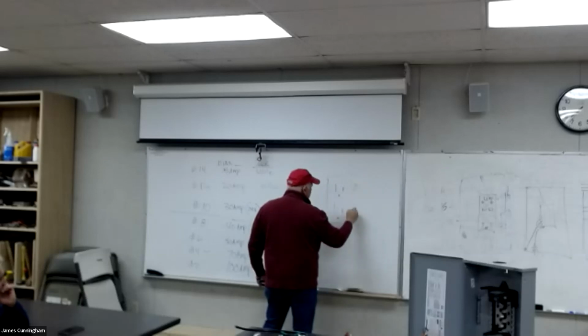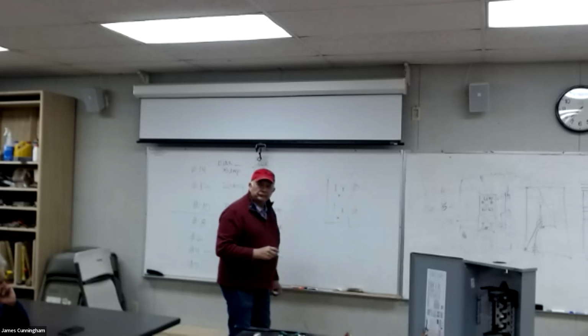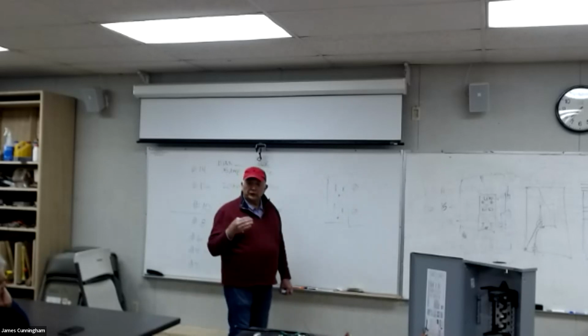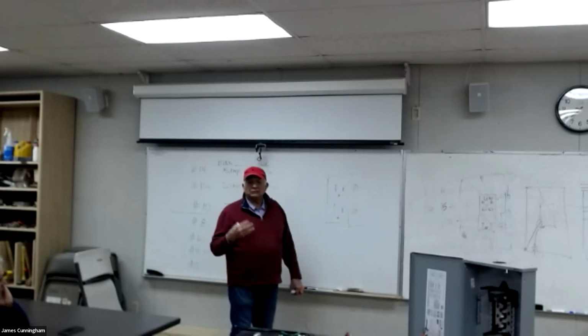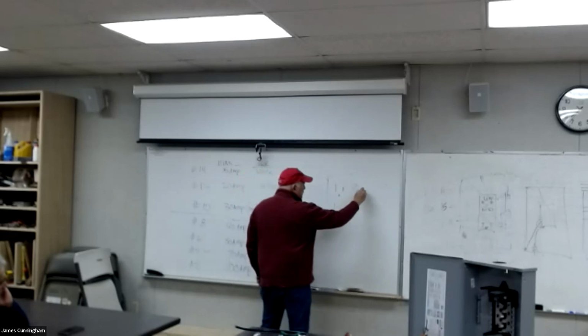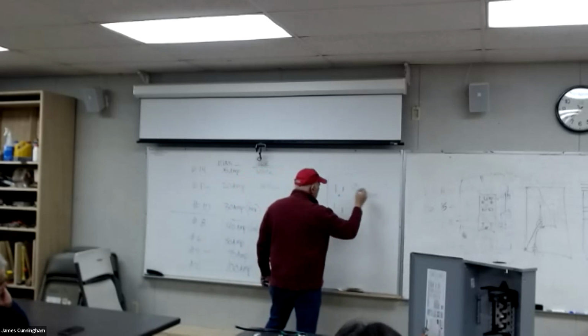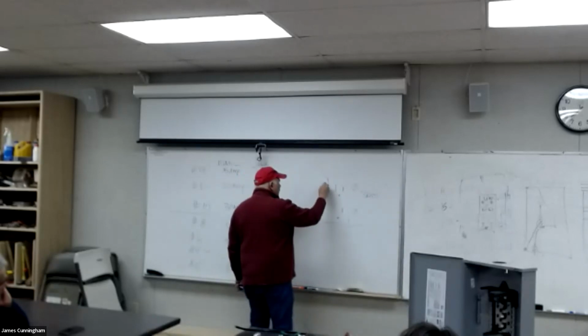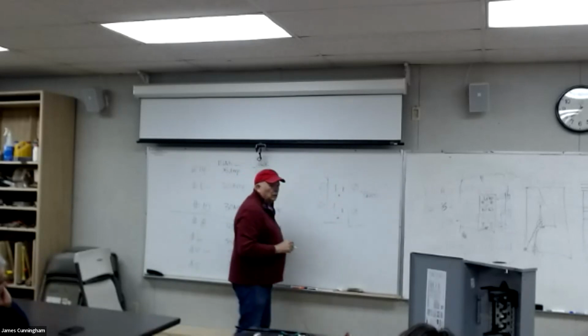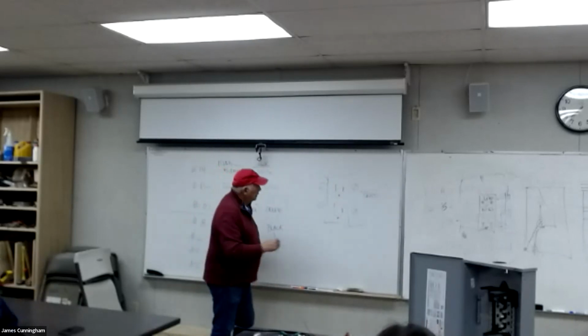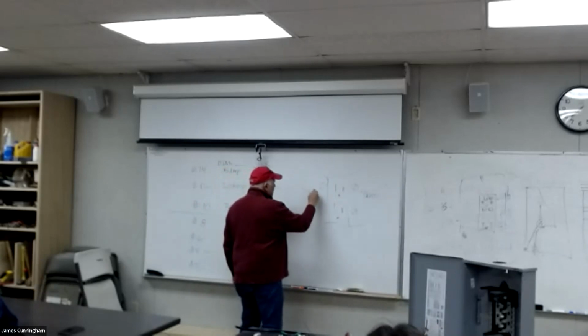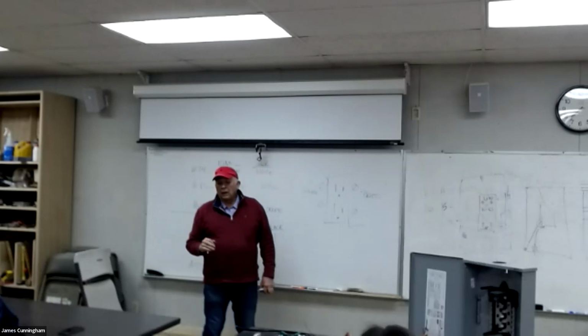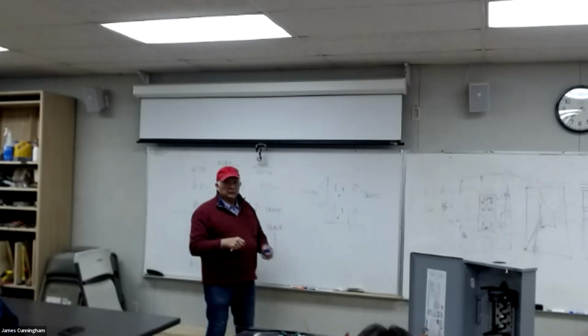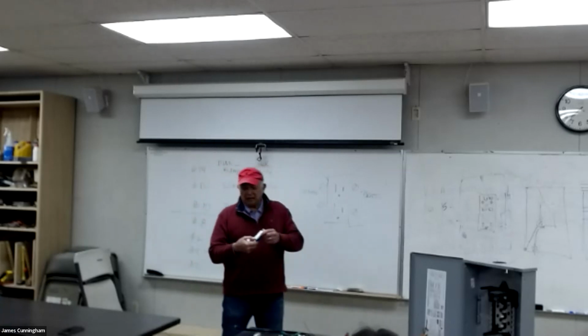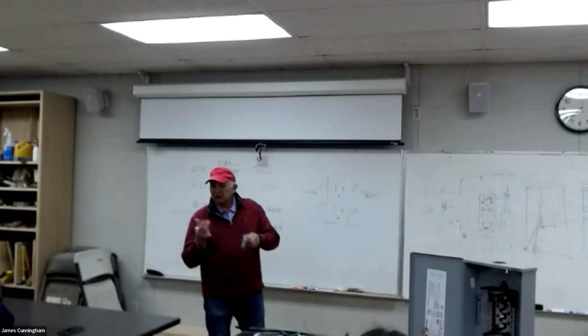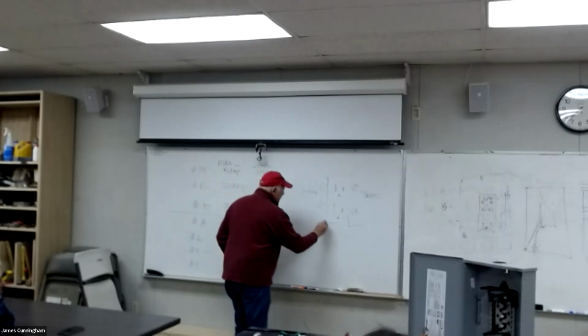The gold or brass screws are on the hot side. So you're going to connect your colored wires, your black wires or your red wires or colored wire of some kind, to these brass or gold ones. On the neutral side, they're going to be silver or chrome. So you're going to put your white wire on the silver screws. Now on the switch, and then on the bottom is a green screw. The green is always ground, right? Always ground. So that's going to be down here.